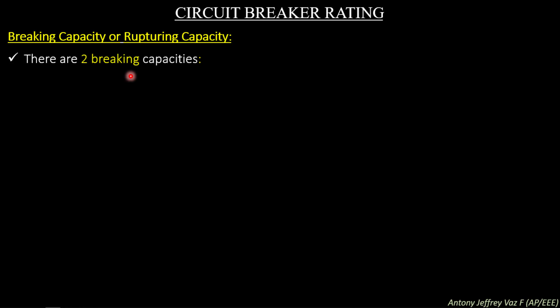So from this context we can say the symmetrical breaking capacity of a circuit breaker is the value of symmetrical breaking current which the circuit breaker is capable of breaking at a stated recovery voltage and a standard reference restriking voltage under prescribed conditions. So these values of current are symmetrical in nature. The symmetry represents the natural voltage wave or natural current wave produced in the generator, and the short circuit wave produced due to the short circuit of a circuit. These two waves look symmetrical in nature. This is known as symmetrical breaking capacity.